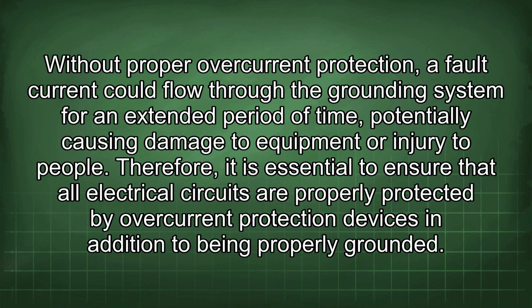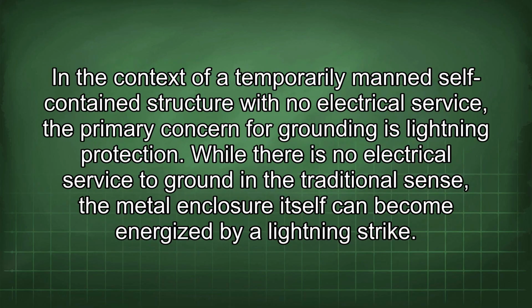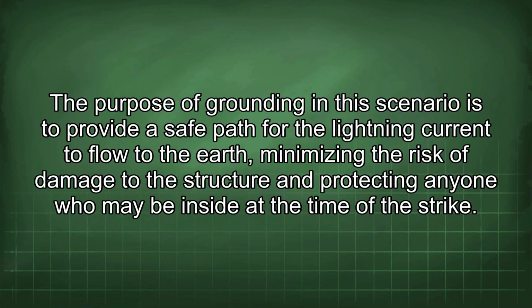Therefore, it is essential to ensure that all electrical circuits are properly protected by overcurrent protection devices in addition to being properly grounded. In the context of a temporarily manned self-contained structure with no electrical service, the primary concern for grounding is lightning protection. While there is no electrical service to ground in the traditional sense, the metal enclosure itself can become energized by a lightning strike.